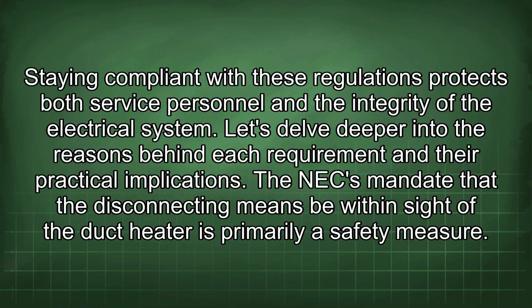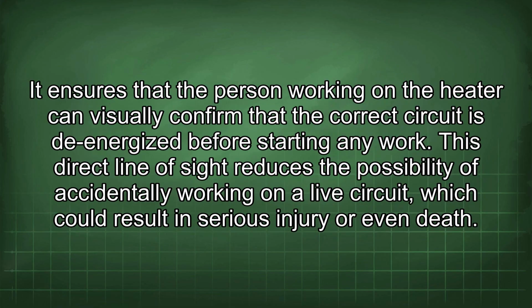The NEC mandate that the disconnecting means be within sight of the duct heater is primarily a safety measure. It ensures that the person working on the heater can visually confirm that the correct circuit is de-energized before starting any work. This direct line of sight reduces the possibility of accidentally working on a live circuit, which could result in serious injury or even death.